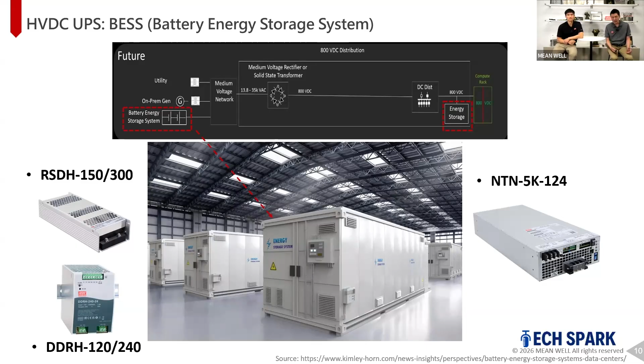Okay, so that is the energy storage system. The next one is we're going to move into the fuel cell backup. Like I said earlier, a diesel generator takes time to start up, and that's why you need energy storage there. Some look into the fuel cell instead. The advantage of using a fuel cell to replace the generator is that it can start up right away, there's no wait time. That means you can get rid of the energy storage.